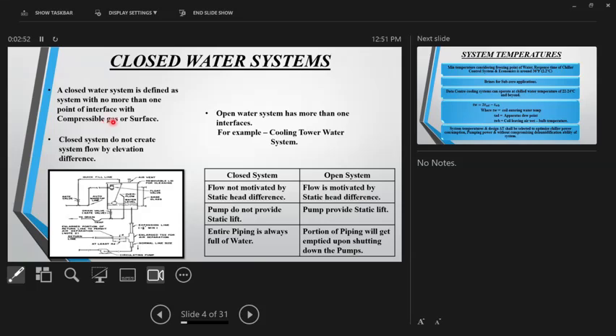Is this definition clear? No more than one interface with compressible gas or surface or atmosphere. So that way, all chill water systems which we talk about are closed water systems. What are the open systems? An example of an open system is the cooling tower water system. Now these systems, as per ISHRAE definition, have more than one interface.